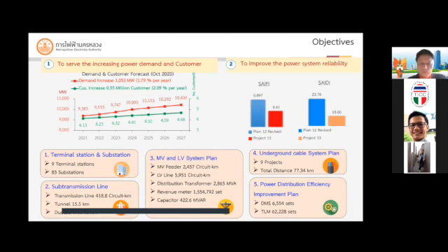SAIFI is the number of failures, while SAIDI is the failure duration. The lower SAIFI and SAIDI are, the better the reliability is. From these 2 objectives, now comes the work content and the amount of work, which consists of 5 sub-plans. Number 1, terminal station and substation system plan for building new power stations and improving existing stations.